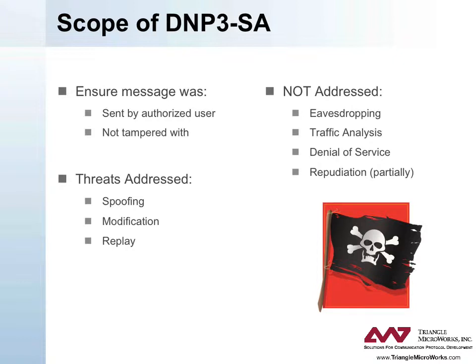DNP3 Secure Authentication is an enhancement through the DNP3 protocol. It's a set of additional function codes, objects, rules, and definitions to be added to the standard protocol, contained within a supplement to Volume 2 of the specification. It's designed to ensure the receiver of a message can verify that the message was sent by an authorized user and verify that it was not modified in transit.